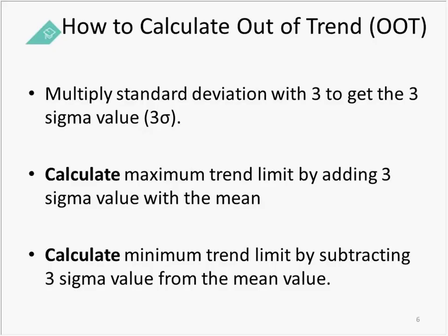Let's talk about how to calculate your out-of-trend results. It is a very simple mathematical equation. You multiply your standard deviation by 3 to get the 3-sigma value. Then you calculate your maximum trend limit by adding that 3-sigma value to the mean — that would be your upper trend limit. To get your lower trend limit, you would subtract that 3-sigma value from your mean.